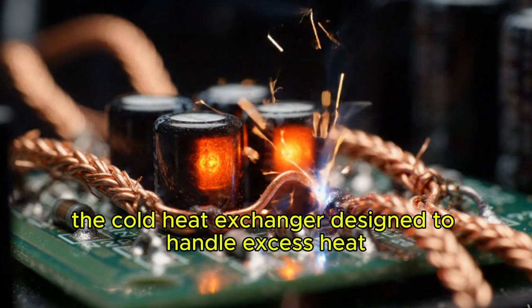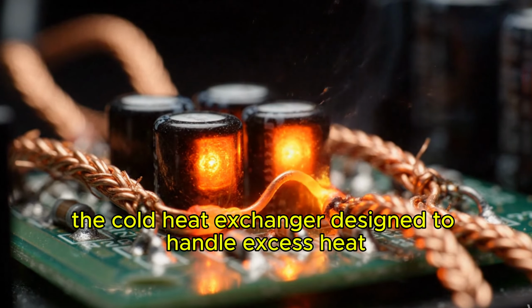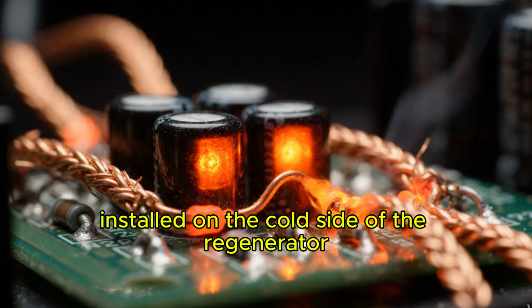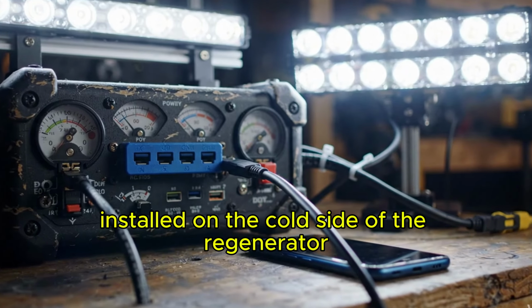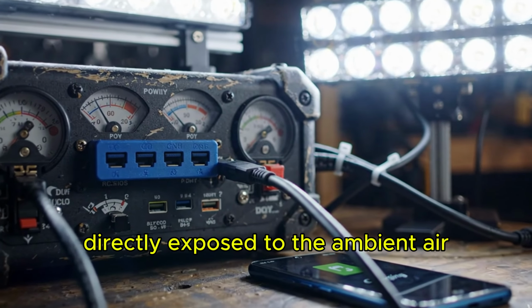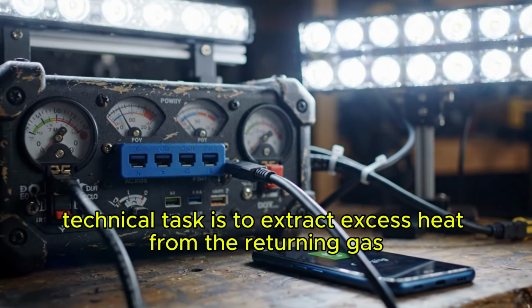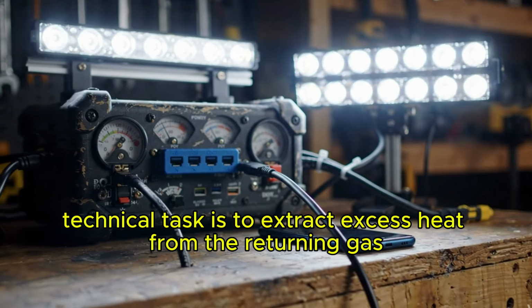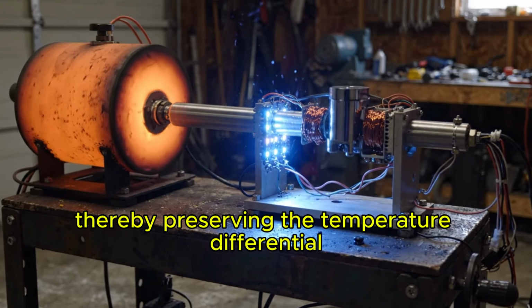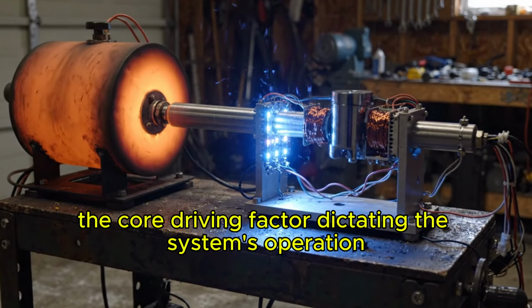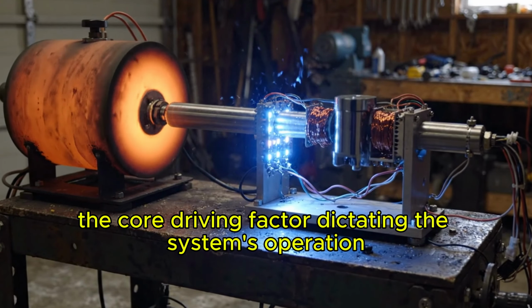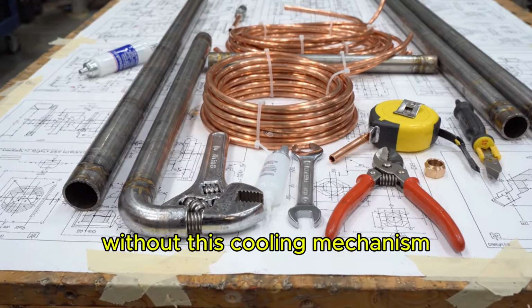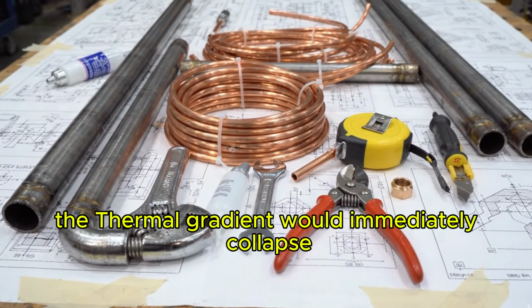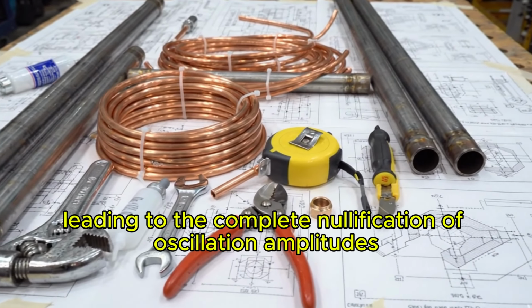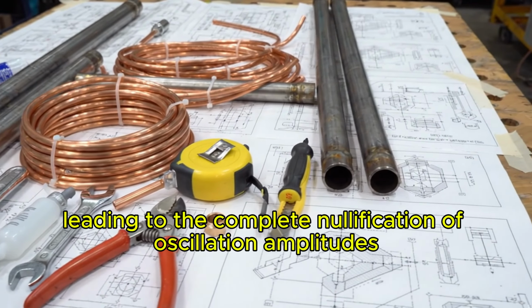The cold heat exchanger, designed to handle excess heat, this is a second copper coil installed on the cold side of the regenerator, directly exposed to the ambient air. Its critical technical task is to extract excess heat from the returning gas, thereby preserving the temperature differential, the core driving factor dictating the system's operation. Without this cooling mechanism, the thermal gradient would immediately collapse, leading to the complete nullification of oscillation amplitudes.